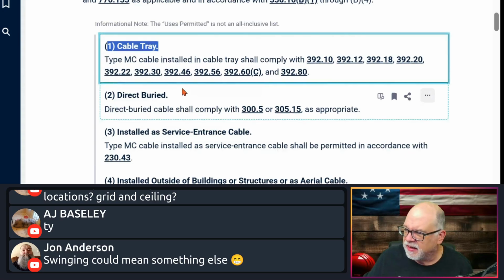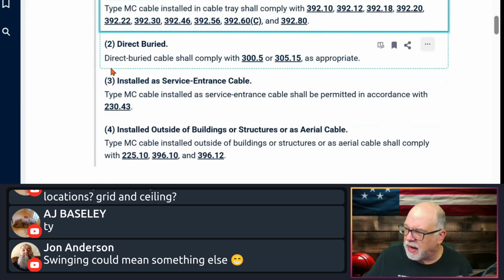That's all that's saying. Direct burial. It's just reminding you that when you do install MC cable with a direct burial rating, with a PVC jacket, because that's going to be a wet location, obviously, direct burial. If it has this direct burial notation on it, which can be printed on the PVC, it says also remember that 300.5 comes into play.